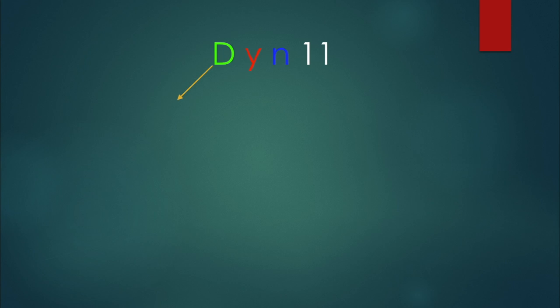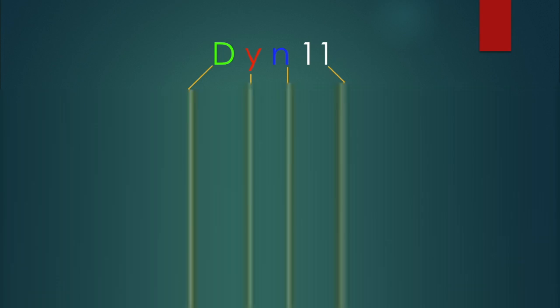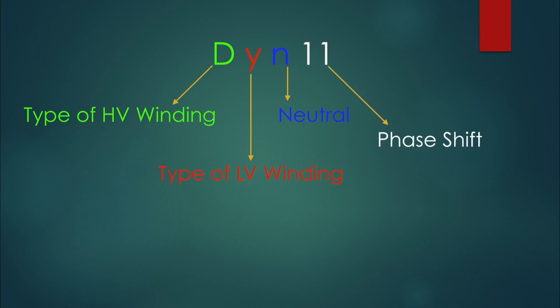The first letter which is mentioned in capital indicates the type of high voltage winding. The second letter indicates the type of LV winding. The third letter indicates the LV winding has neutral point as well and the numbers indicates phase shift between them.